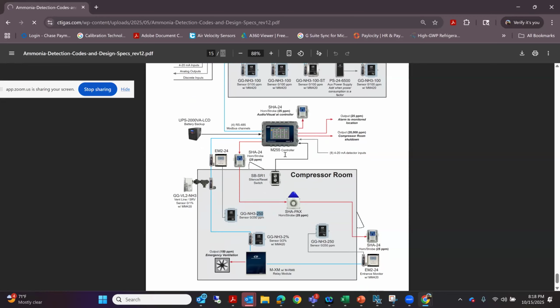So when you're monitoring these systems, by code, that monitoring could be to the fire department. They could be saying, hey, we want a call at 25 ppm. Or they could say, well, we don't want you to be bothered at 25 ppm. Start calling us at 150, because we don't want to send the fire department down there 4 times a year just because you're changing oil and you accidentally didn't get the fans turned on for some of these sensors, right? And so that's kind of what we're used to seeing for some of these output functions.